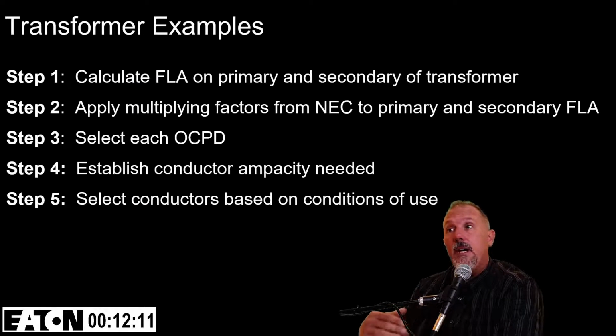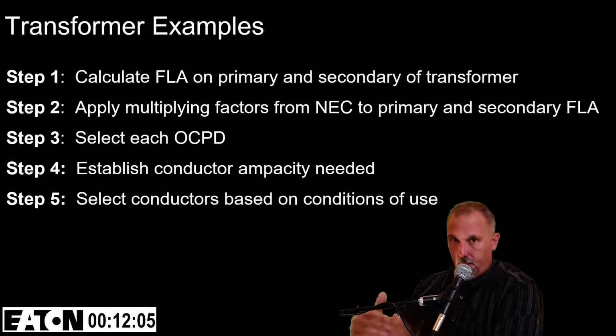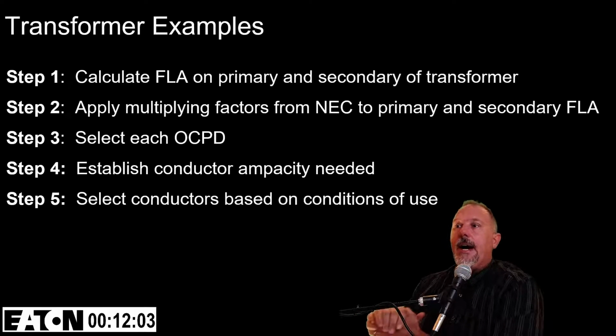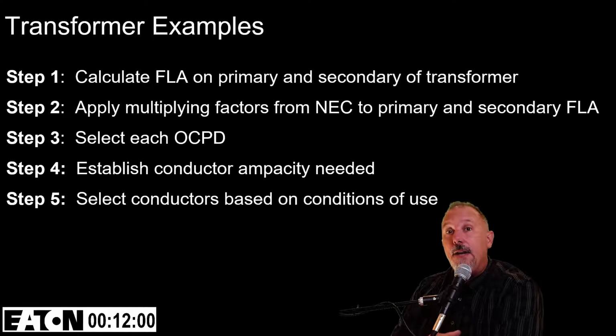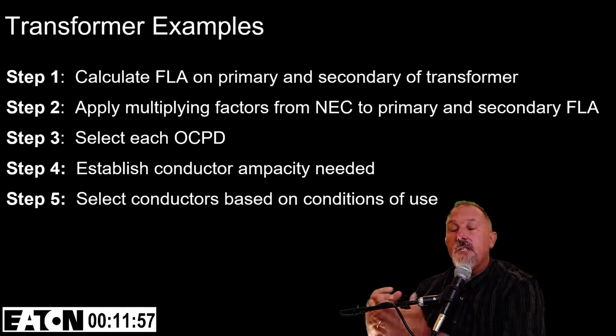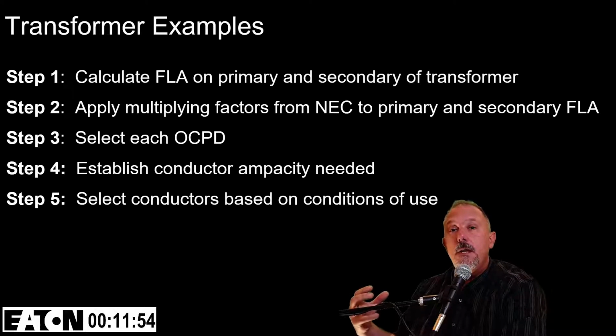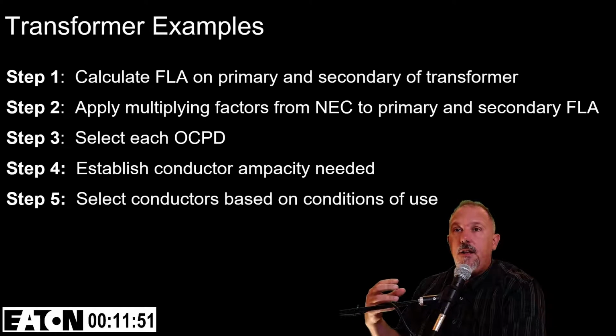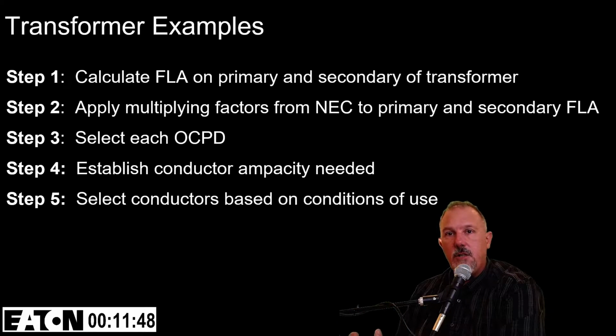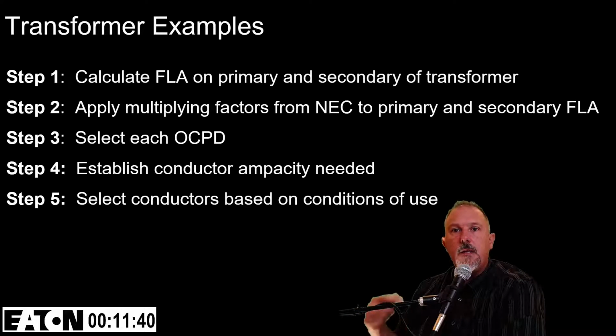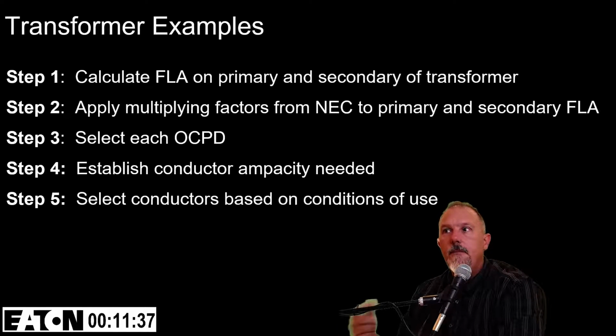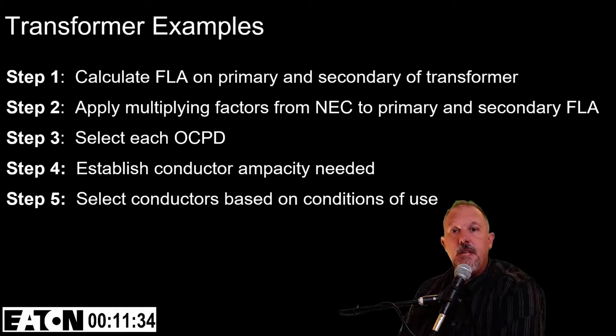Now, my steps include first calculating the full load amps and applying the multiplying factors from the National Electrical Code. I don't pick the conductor right off the bat, and the reason is because selecting your overcurrent protective device is the driving factor, and it's not about what size conductor you have. It's about how much full load amps you have and what your inrush currents are. So you don't make the mistake of picking the conductor first and then picking your overcurrent protective device. You have to pick that overcurrent protective device based upon the tables, and possibly we're going to show some time current characteristic curves as well.